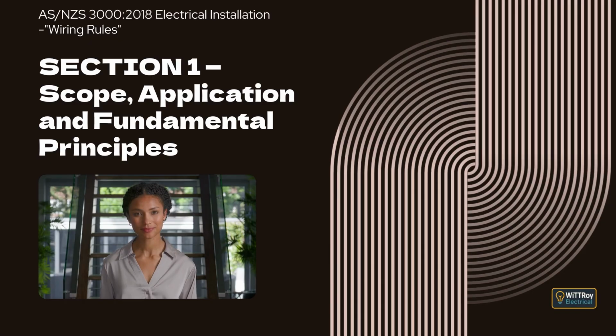Fourth, for PELV circuits, live parts must be protected against direct contact. This can be done by barriers or by insulation, unless the voltage is extremely low. In dry areas, this limit is 25 volts AC or 60 volts ripple-free DC. Where a person may have a larger contact area with the body, such as wet or conductive locations, the voltage limit is 6 volts AC or 15 volts ripple-free DC.